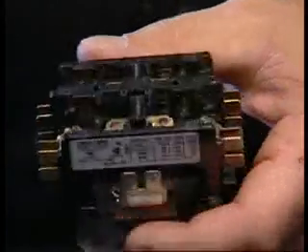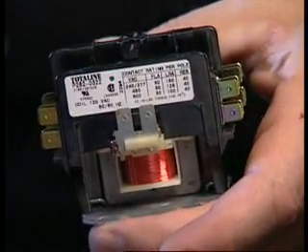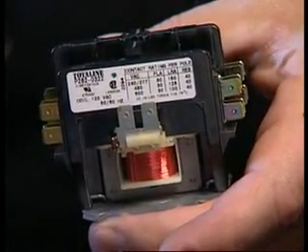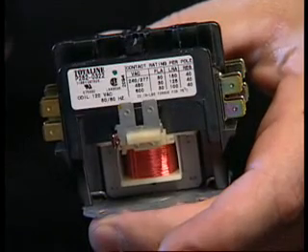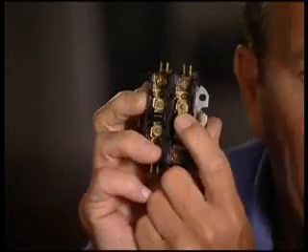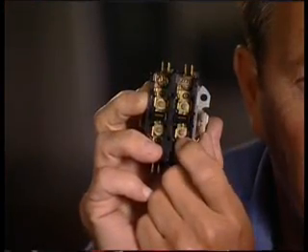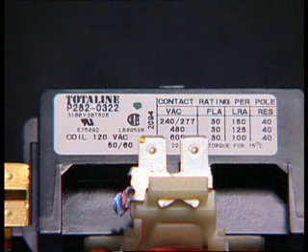The two main components of the contactor are the coil and the contacts. The contactor coil generates a magnetic field, which pulls the contacts closed, energizing the system load that's being controlled. Contacts on the contactor are connected to an armature that helps ensure that all sets of contacts open and close at the same time. Contacts are rated by their current carrying capability. Large loads require contactors with a high current rating.